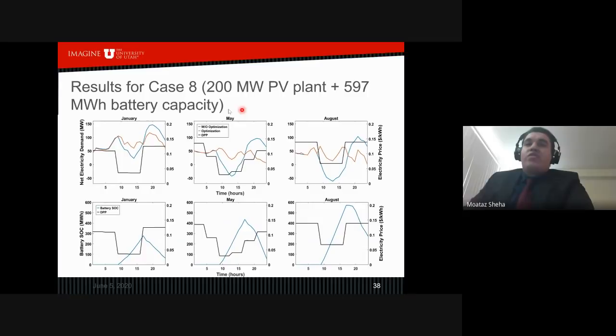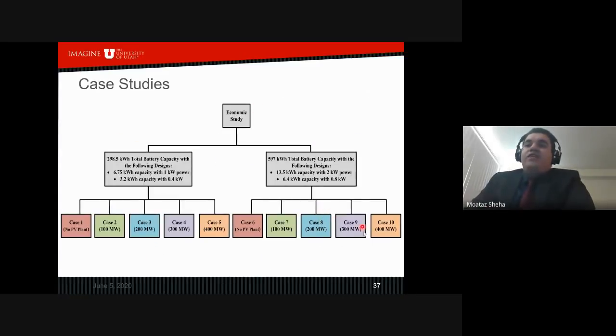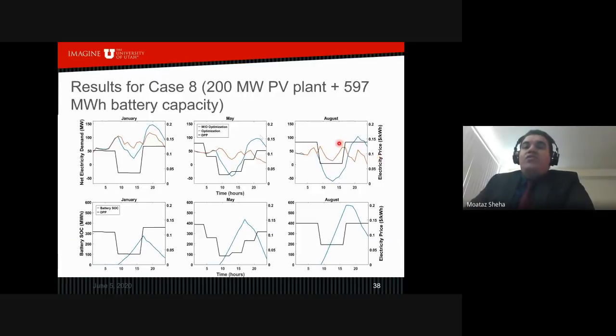So for the results, I'm only looking at case 8 - actually the best results are for case 8 and case 9, and I'll explain why. For case 8, I'm showing results for 3 months: January representing winter, August representing summer, and May representative of spring and fall. You can see the curve getting flat, close to 0, in case 8, which is a 200 megawatt PV plant with this battery capacity. The curve flattens around 0 in May and August, but in January it's shifted upward a bit because of a lot of heating happening, which shifts the curve up.